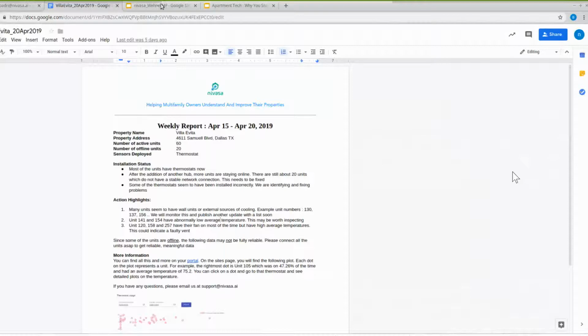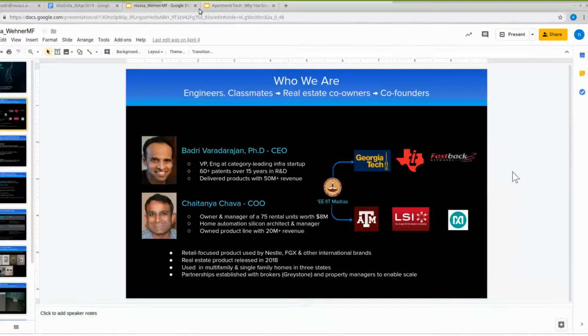For example, you can set the boundary, the upper and lower limit. The tenant can still change it, but whatever they change, it will go back to the cycle, let's say the next day. They go back to the same cycle again. Correct. And you decide what you want to go back to. If you want to save more energy, you can set it aggressively.